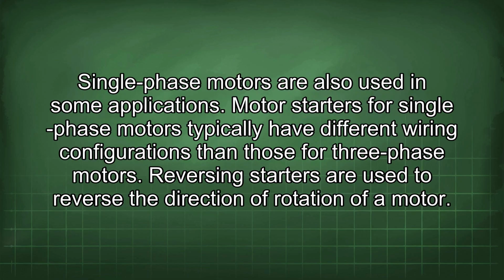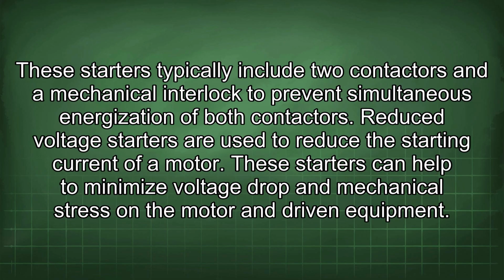Single-phase motors are also used in some applications. Motor starters for single-phase motors typically have different wiring configurations than those for three-phase motors. Reversing starters are used to reverse the direction of rotation of a motor. These starters typically include two contactors and a mechanical interlock to prevent simultaneous energization of both contactors.